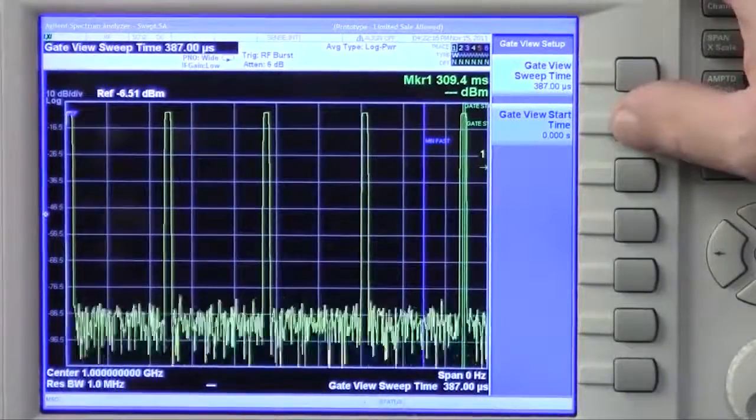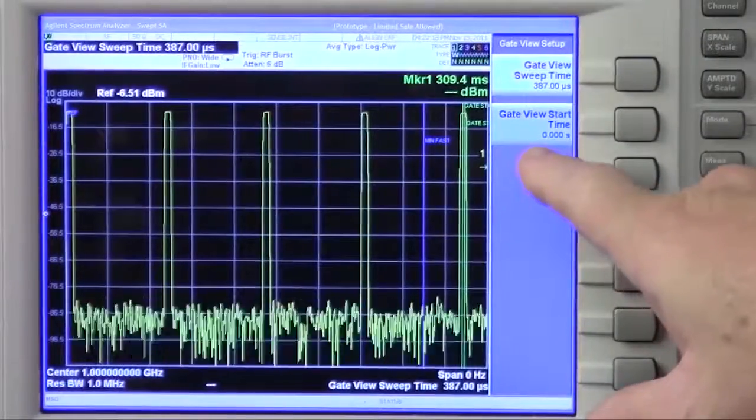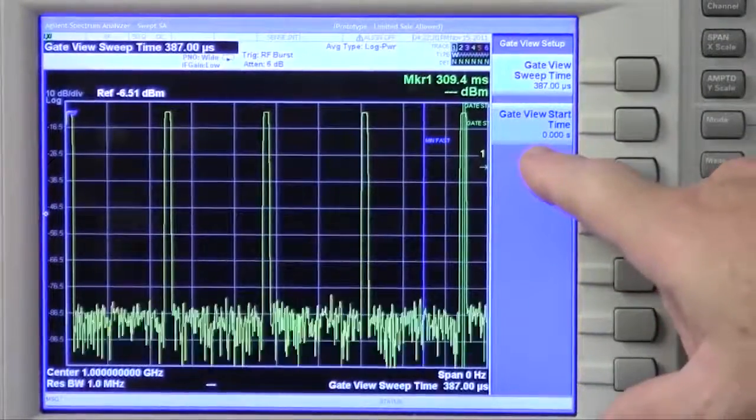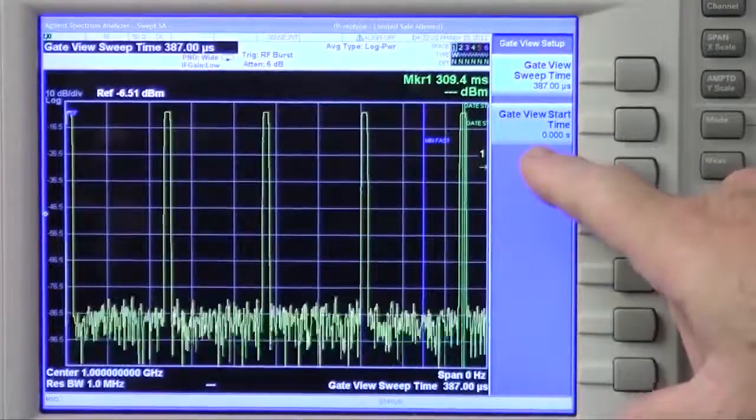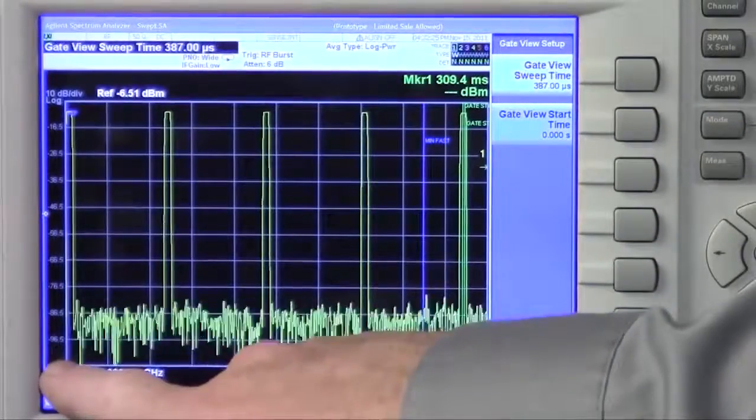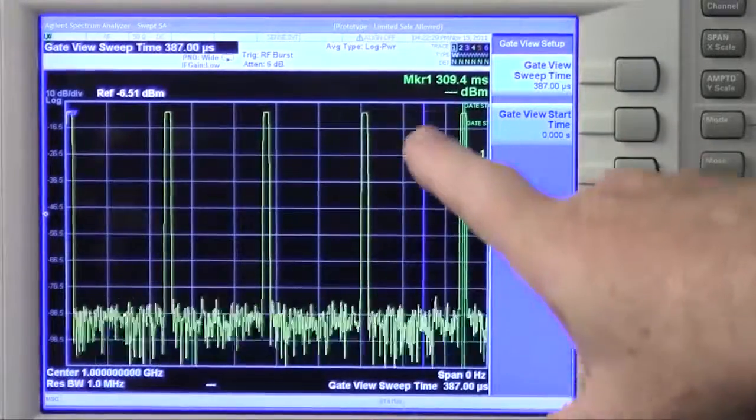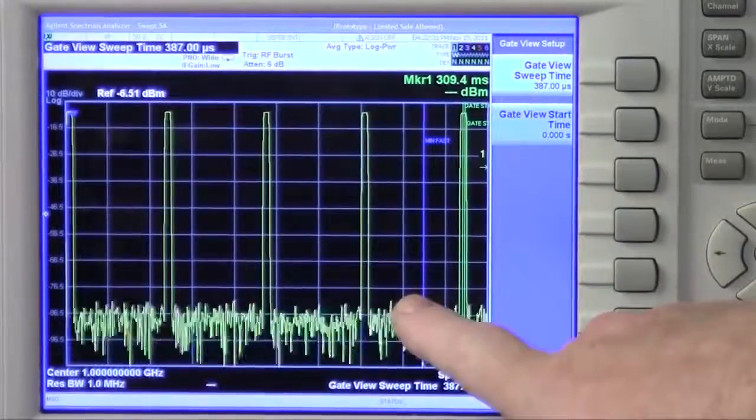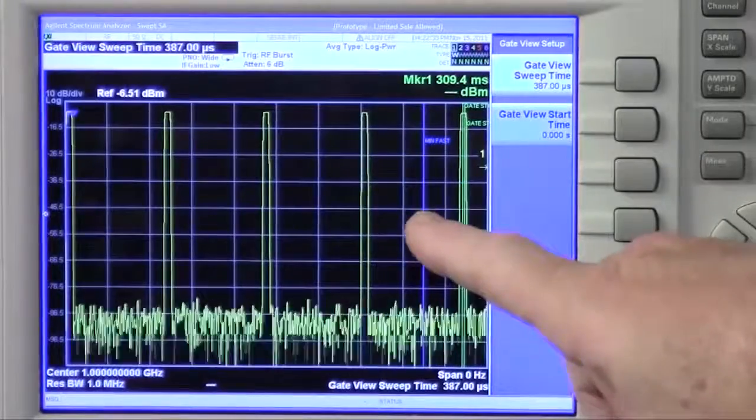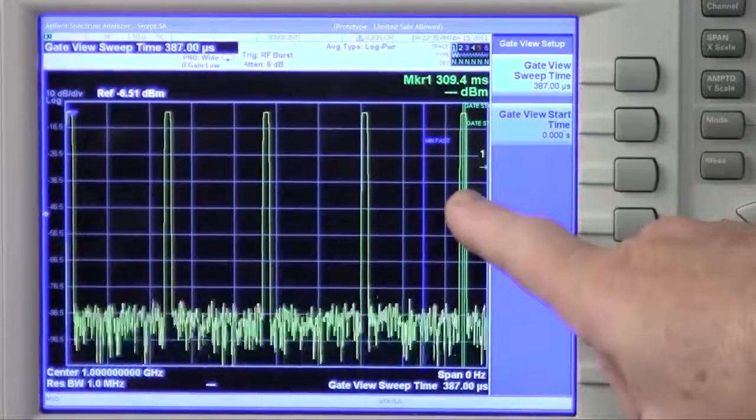To solve this problem, a new parameter called gate view start time has been added. The gate view start time is the time at the left side of the screen. So what we can do now is set the gate view start time to near what the min fast time is, and then we'll have plenty of range to set our gate view sweep time.